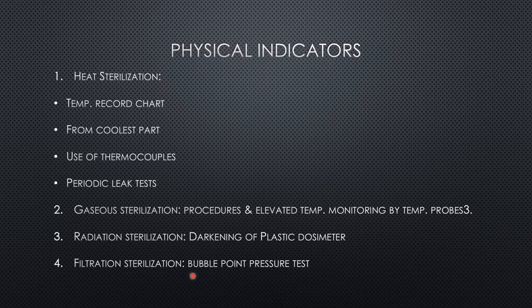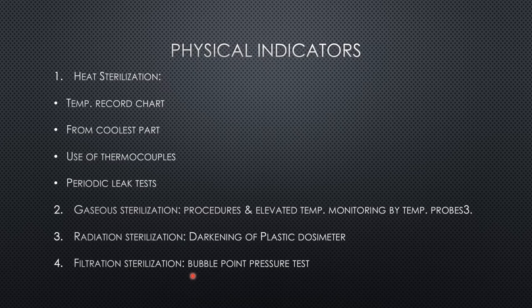In case of filtration sterilization, the bubble point pressure test is performed. This test is used to determine the pore size of filters and to check the integrity of certain types of filter devices immediately after use. The basic principle is that a wetted filter is subjected to an increasing air or nitrogen gas pressure differential. The pressure difference is recorded when the first bubble of gas breaks away from the filter, which is related to the maximum pore size.